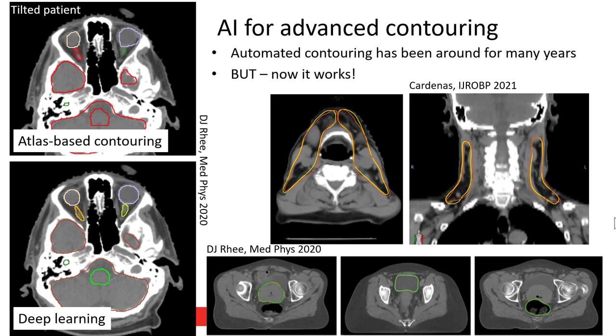We've had automatic contouring in treatment planning systems for many years. But our common experience is that we might apply those tools and often they wouldn't be quite right—we'd have to make edits, and sometimes we'd just delete them and start from scratch. So why is that, and why is it different now? Atlas-based contouring uses an atlas of previously contoured patients, deformably registered to your current patient to pull contours over. That was the state of the art until just a year or two ago. It works well under certain circumstances, but when your current patient's anatomy differs from the atlas, it fails.